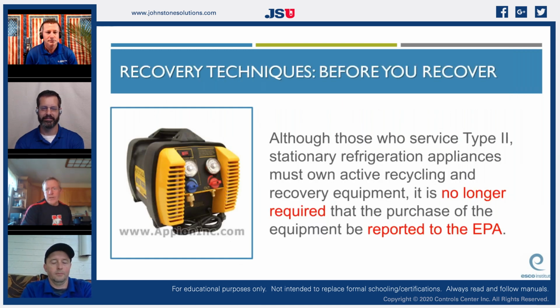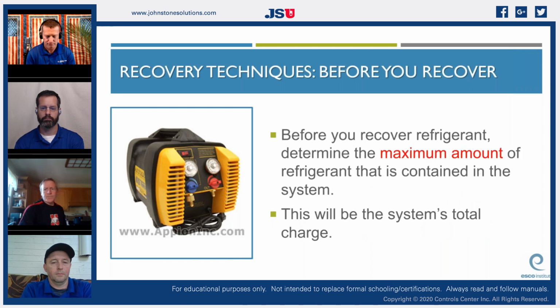This is kind of interesting. A lot of guys don't know this. Those servicing type 2 stationary refrigerant appliances must own active recycling and recovery equipment. And I tell every heating and air company, every maintenance department that does HVAC, you have to have a recovery machine on site that will stand alone and remove the refrigerant from the unit with nothing operating on the unit. So you could take all the electrical controls out of it. This machine can take the refrigerant out of it. But once you purchase one, you do not have to report it to the EPA. They expect you to have it, but you don't have to send them a letter telling them you bought one.